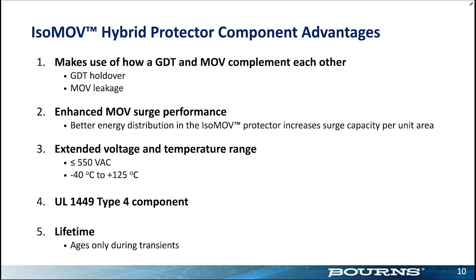Number 3, higher voltage, extended temperature range, 125 degrees C is hard to find for components like this. These will work up to that higher temperature. These are recognized as a UL 1449 Type 4 component. Lifetime is interesting because there's no leakage. Normally, this MOV is not aging. It's not sitting there aging, just even with no surges like a normal MOV would. This thing will only age during the surges, during these transients. So the lifetime is much longer than you'd find in a normal MOV.